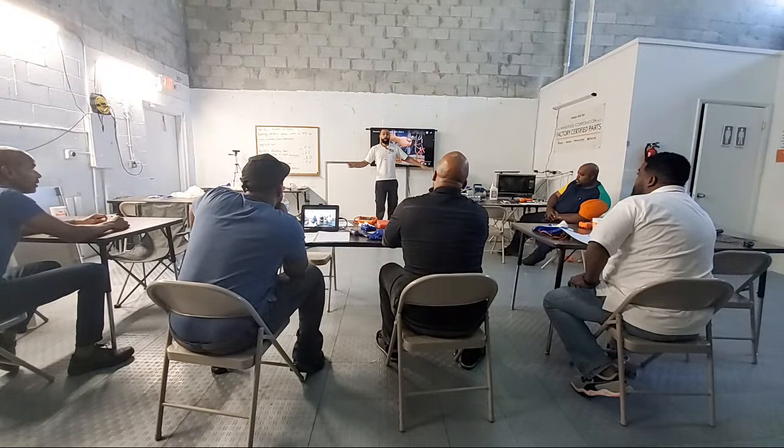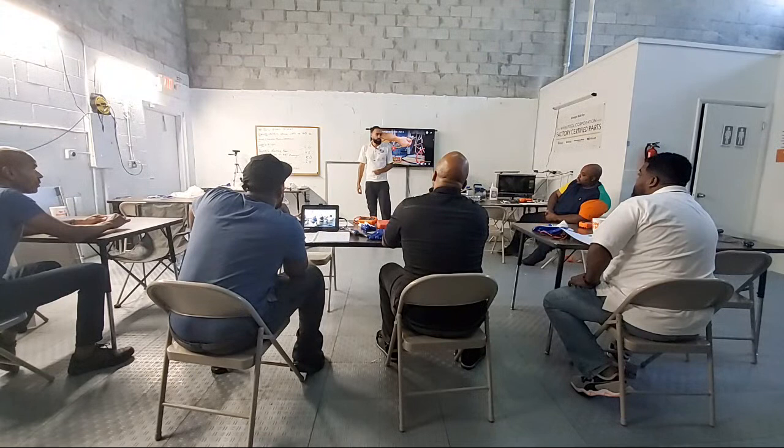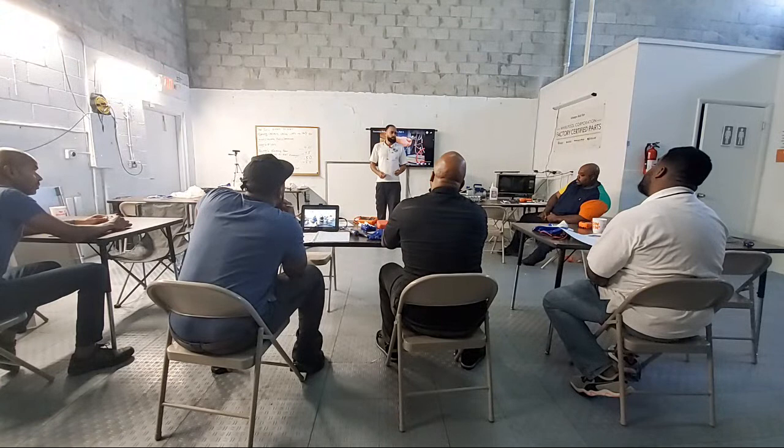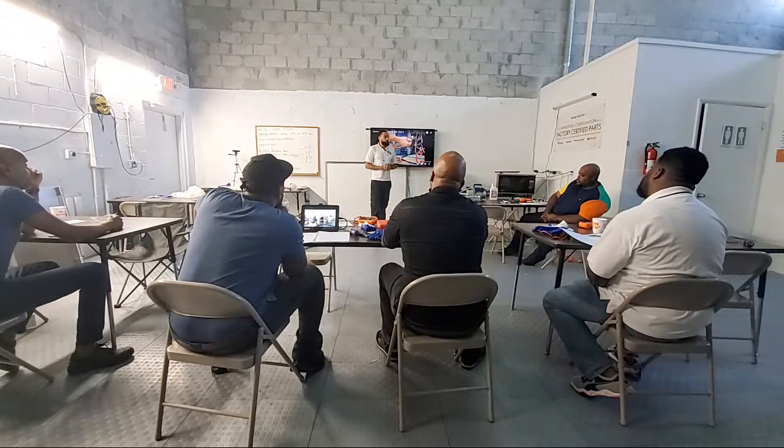Oh, for the wire. You'll notice that your DCs, the wires are a little slimmer than your ACs. But don't go off of that. Always go off of the identification on the thing. But more than likely, rule of thumb, if you see smaller, it's generally DC, but you can still check with your phone. All right, so our condenser fan's running.